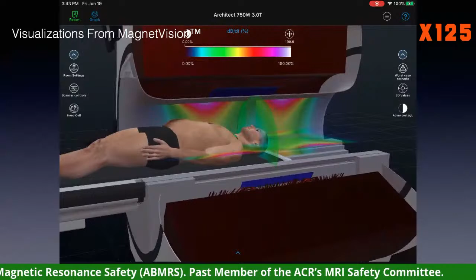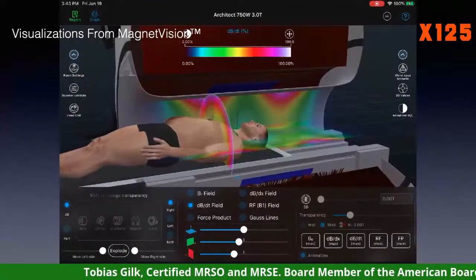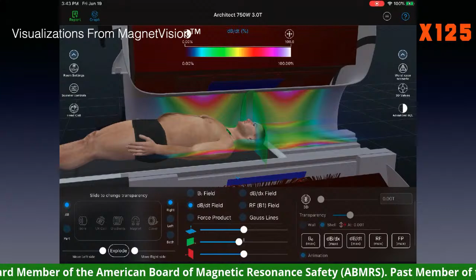So maximum gradient amplitudes. This patient positioned for a brain, the maximum gradient amplitude that their tissues will experience is in the upper arm. And this is very counterintuitive, particularly to people who come to MR from an X-ray background, where we're very careful to make sure that the energies associated with capturing the image only strike the anatomy where we're capturing the image. MR is different because the maximum energies are in locations other than where we're capturing the image, and we have very little ability to modify that. We can't modify it at all for the static field. We can't modify the spatial distribution at all for the time-varying gradients.